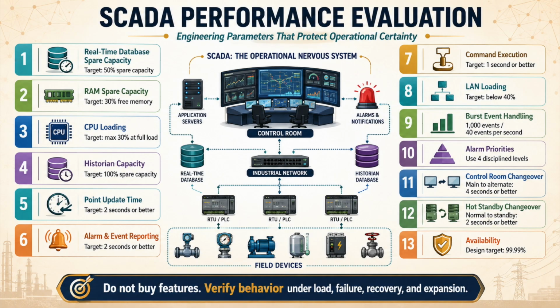A strong design target is maximum 30% CPU load at full operating load, because critical infrastructure needs processing margin when conditions stop being normal. High CPU load creates alarm latency, screen lag, delayed polling, slow commands, historian backlog, failed synchronization, and operator distrust. And once operators believe screens are late, they hesitate, cross-check, call field personnel, and lose confidence in control room authority.